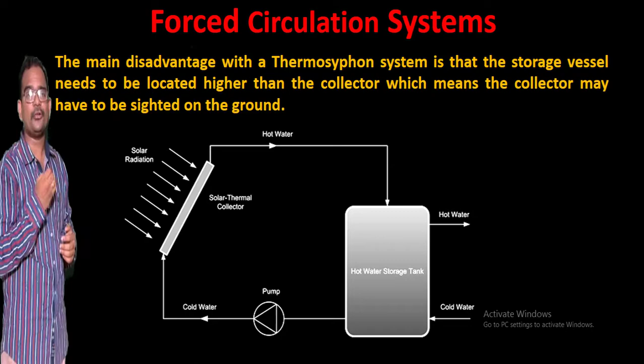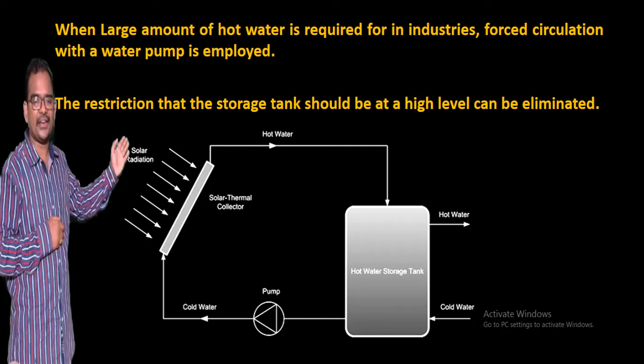When a large amount of hot water is required for use in industries, forced circulation with a water pump is employed. The restriction that the storage tank should be at a high level can be eliminated if I go for a forced circulation system. I can keep them side by side. Water from a storage tank is pumped through a collector where it gets heated up and then flows back into the storage tank. Whenever the hot water is withdrawn for use from the tank, automatically the cold makeup water will take its place at the bottom.